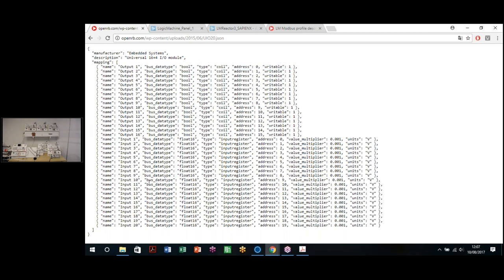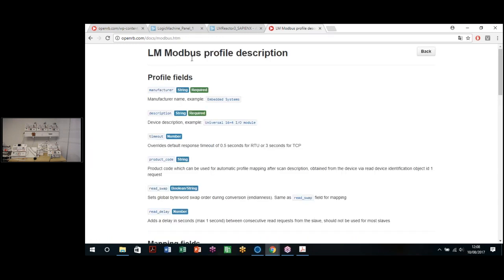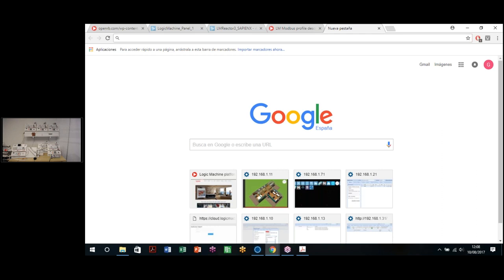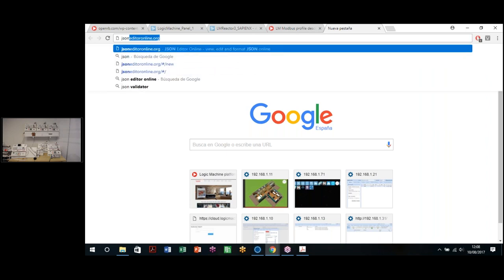In this case, as you can see, we have 20 outputs and inputs, and we can assign to every object output a Boolean data type, depending on which type of object we have, the type of register that we're using, in this case a coil, the address, and whether it's writable or not writable. All the information you can find in the Modbus profile description. Okay, for this thermostat, I'm going to use an online editor. It's free, and I like it very much. In this case, it's the JSON editor online.